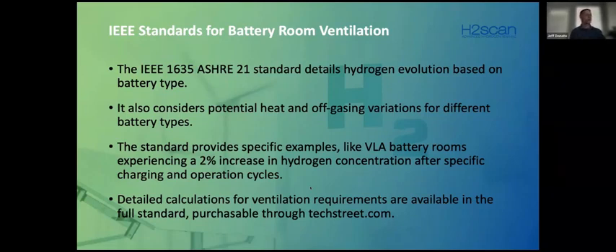I have an example coming up in a few slides from now. But basically, it considers the heat and off-gassing variation from the battery type, and it also provides specific hydrogen concentration examples for charging and operating cycles. What that means is it gives you the best case scenarios on float voltage, and then it also goes through the worst case scenarios, such as boost equalized charge, thermal runaway, and charger runaway. We'll go over that in a few minutes. These detailed calculations provide guidance to design ventilation systems that meet the specific battery room, whether it be a substation or a SCADA system or whatnot. So there's definitely some help out there, and that document can be found either on IEEE or on TechStreet.